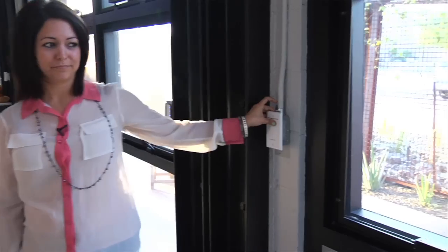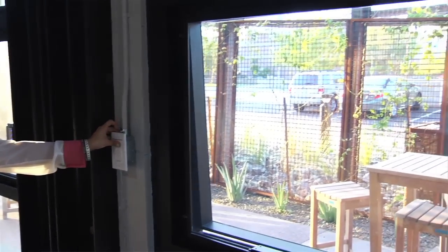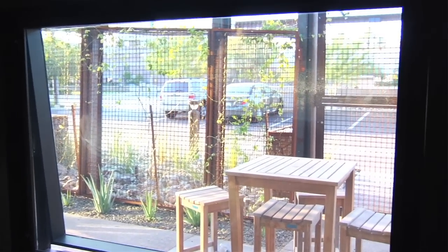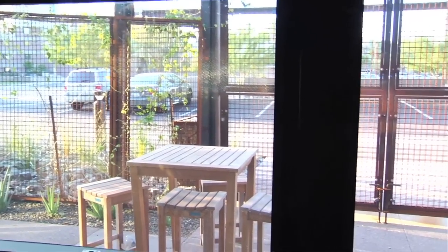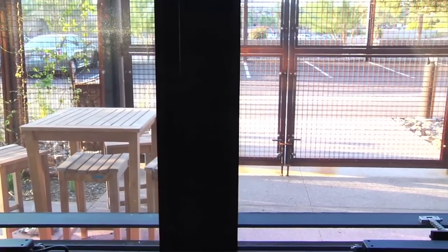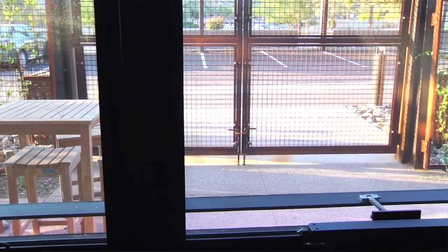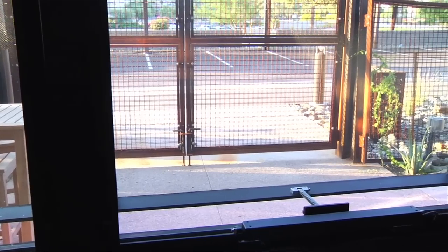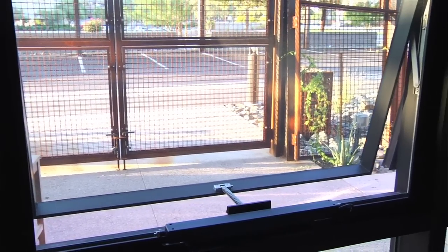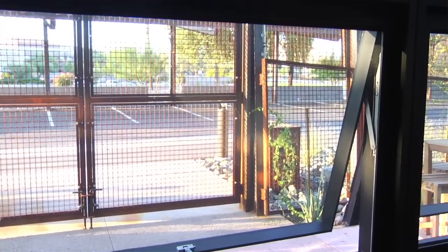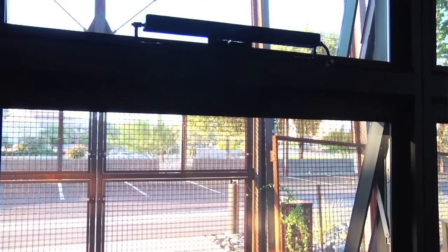Our passive cooling system has 4 main legs. The first leg is bringing the outdoor air inside through our operable windows. We have operable windows on the north and the east elevations of the space. They operate on actuators. They open when the temperature outside is the temperature we want to bring inside. So obviously in the wintertime, if it's too cold, we don't want to bring it in. In the summertime, if it's too hot, we don't want to bring it in. But they open at the right times.